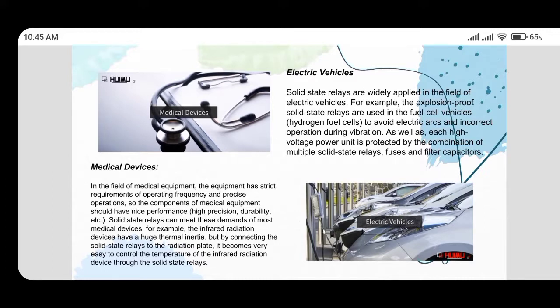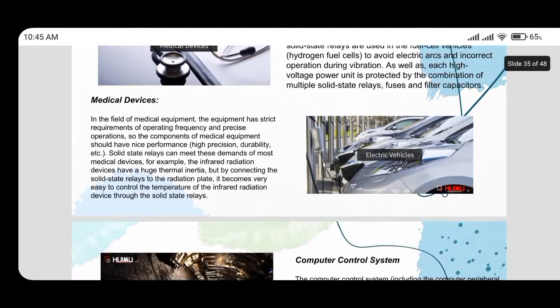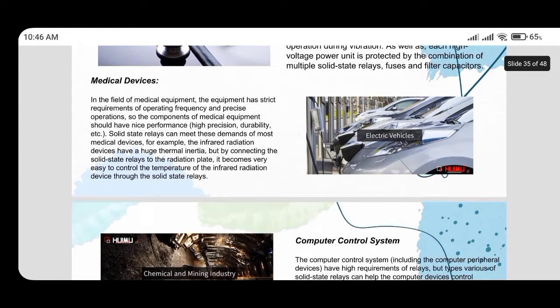Medical devices. In the field of medical equipment, the equipment has strict requirements for operating frequency and precise operation. So the components of medical equipment should have nice performance, high precision, durability, and so on. Solid state relays can meet these demands of medical devices. For example, infrared radiation devices have huge thermal inertia, but by connecting solid state relays to the radiation plate, it becomes very easy to control the temperature of the infrared radiation device.